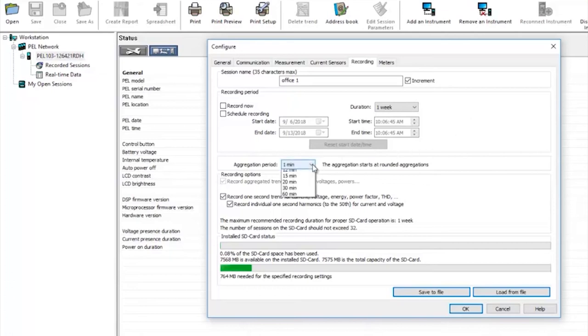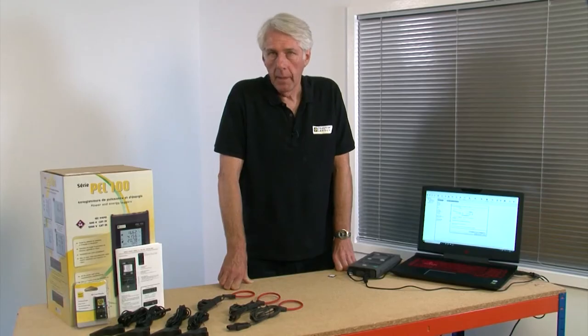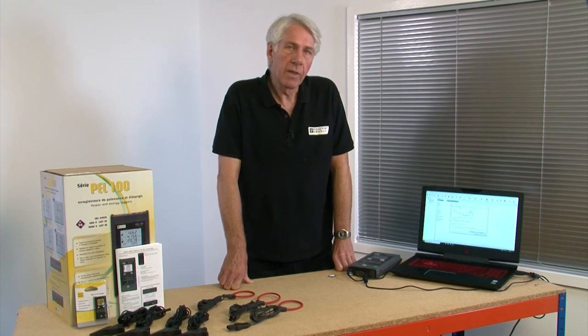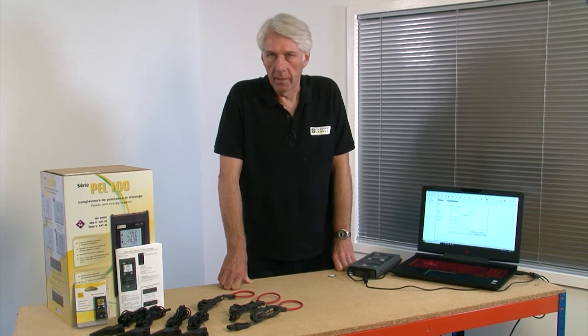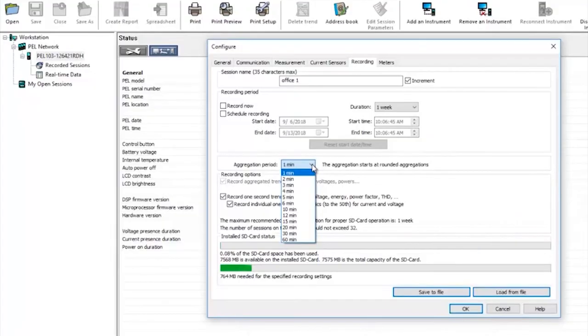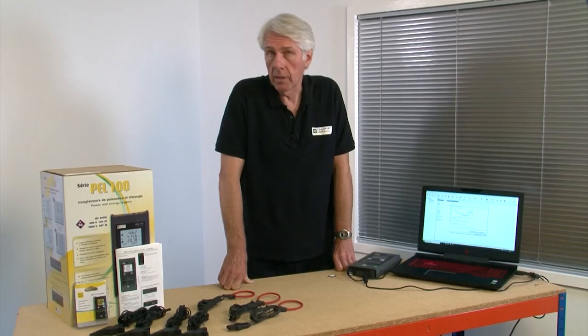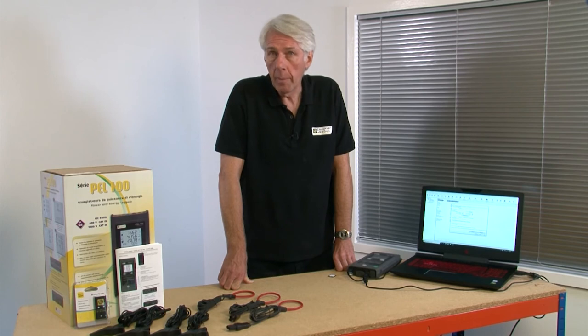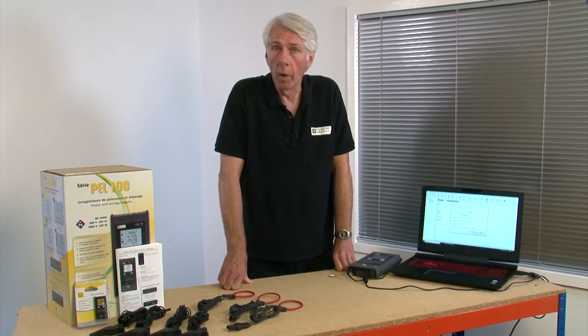Next you will need to choose an aggregation period. The instrument takes samples every 78 microseconds. However this would create an enormous amount of data. By setting an aggregation period the PEL will plot a value which is an aggregate of all those samples over for example a one minute period. The aggregation period can be set as high as 60 minutes. Nothing is overlooked however as it will still store an absolute minimum and maximum value within that one minute plot.